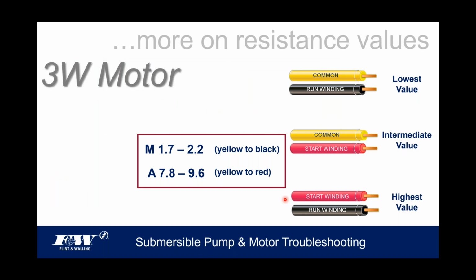So when we look at these values, the yellow and black, which was that M value, we can refer to as the lowest value. Come down to the next one, the yellow and the red, which is your common and start windings. That's your A value, the values under the A. That's what we would call the intermediate value. And then if you put your probes on the start and run windings together, the red and black wires, that's going to be the highest value. Even though we only published two values, we'll have three of them over here, right?